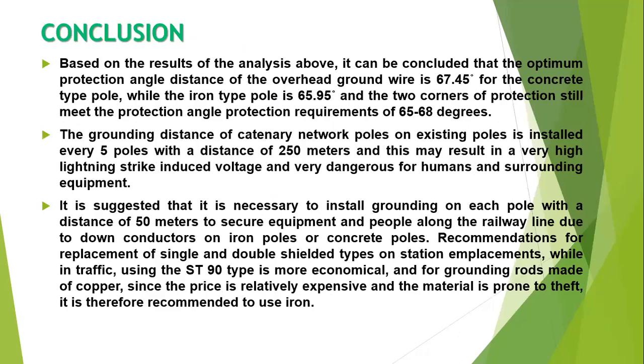Conclusion. Based on the result of the analysis above, it can be concluded that the optimum protection angle of the overhead ground wire is 67.45 for the concrete type pole, while the iron type pole is 65.95, and the two protection angles still meet the protection angle requirement of 65 to 68 degrees.